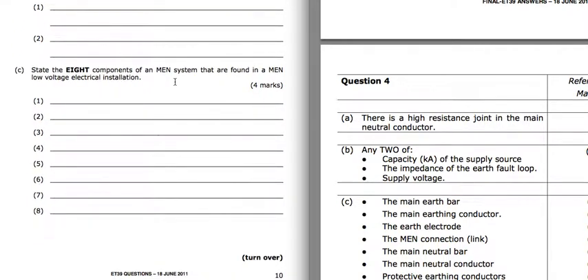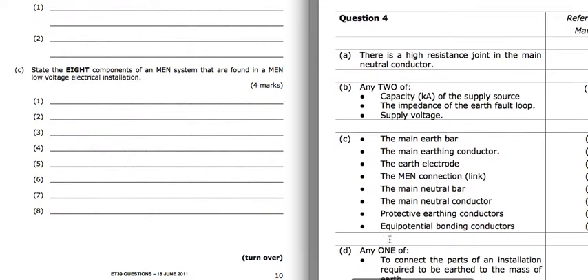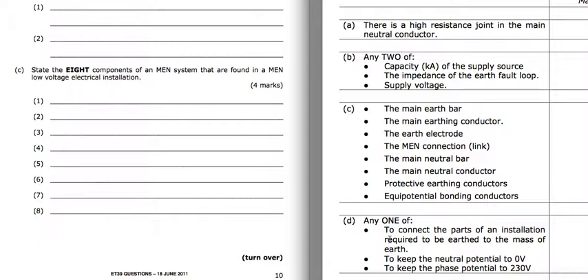State 8 components of an MEN system that are found in an MEN low voltage electrical installation. So you need to know the MEN system. You need to be able to draw it and to describe it and to name the parts. So the main earth bar, main earthing conductor, earth electrode, MEN connection link, the main neutral bar, the main neutral conductor, protective earthing conductors, and the equipotential bonding conductors. So they are the components that will make up the MEN system.